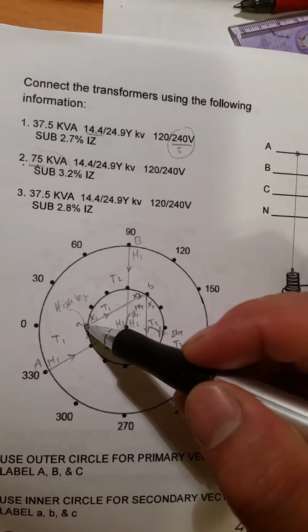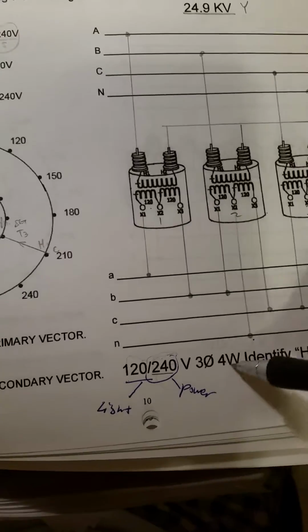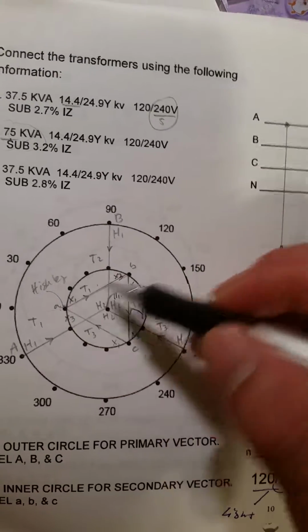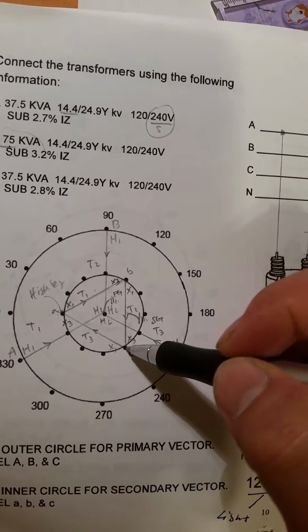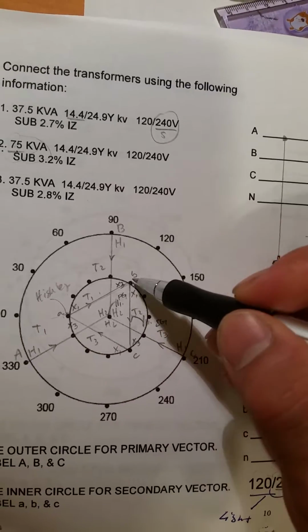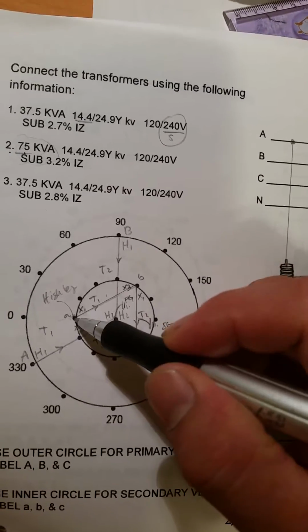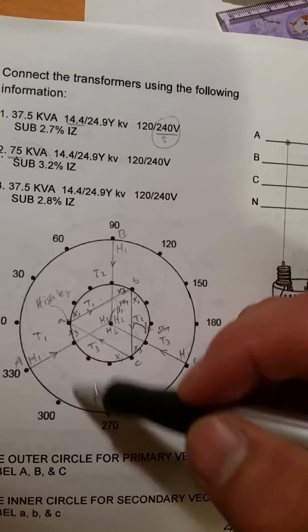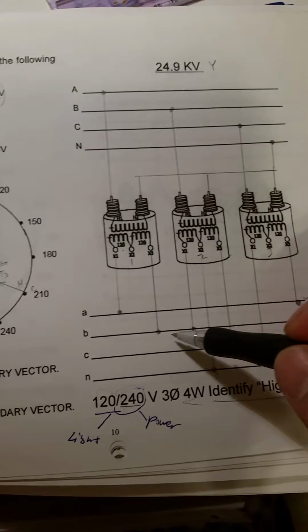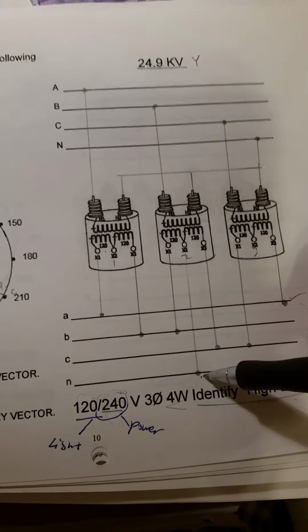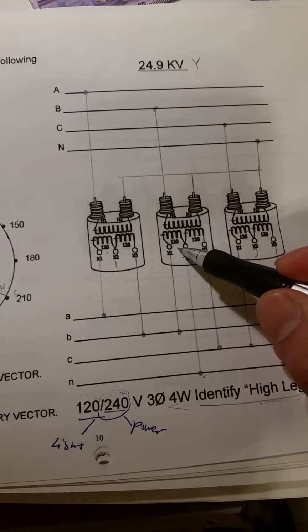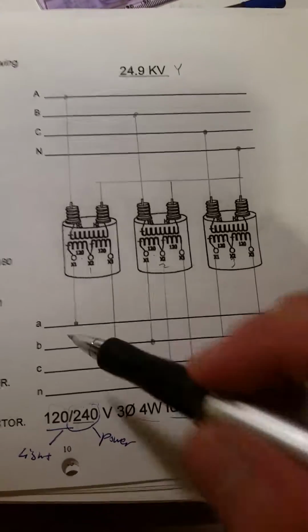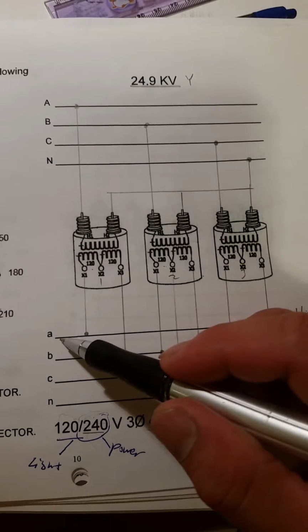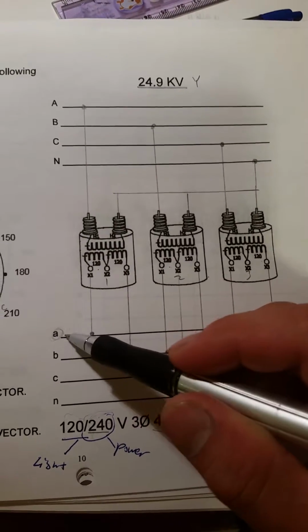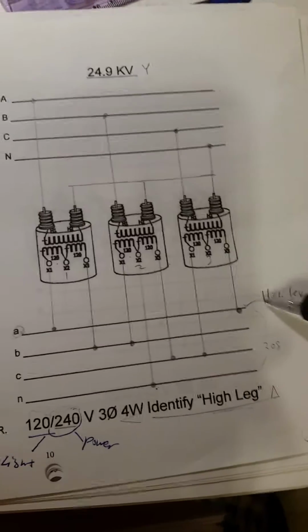So in a building, you're gonna have 4 wires coming in - this wire, that wire, and that wire, and that wire. Well, you don't want to get mixed up with this one to that one. Because this is gonna be 208 to ground - A phase to ground is gonna be 208, B phase to ground is gonna be 120. So that's why it's important to mark this phase with the orange tape, because that's always going to go back to that, because it's going to be 208. That's how I did that.